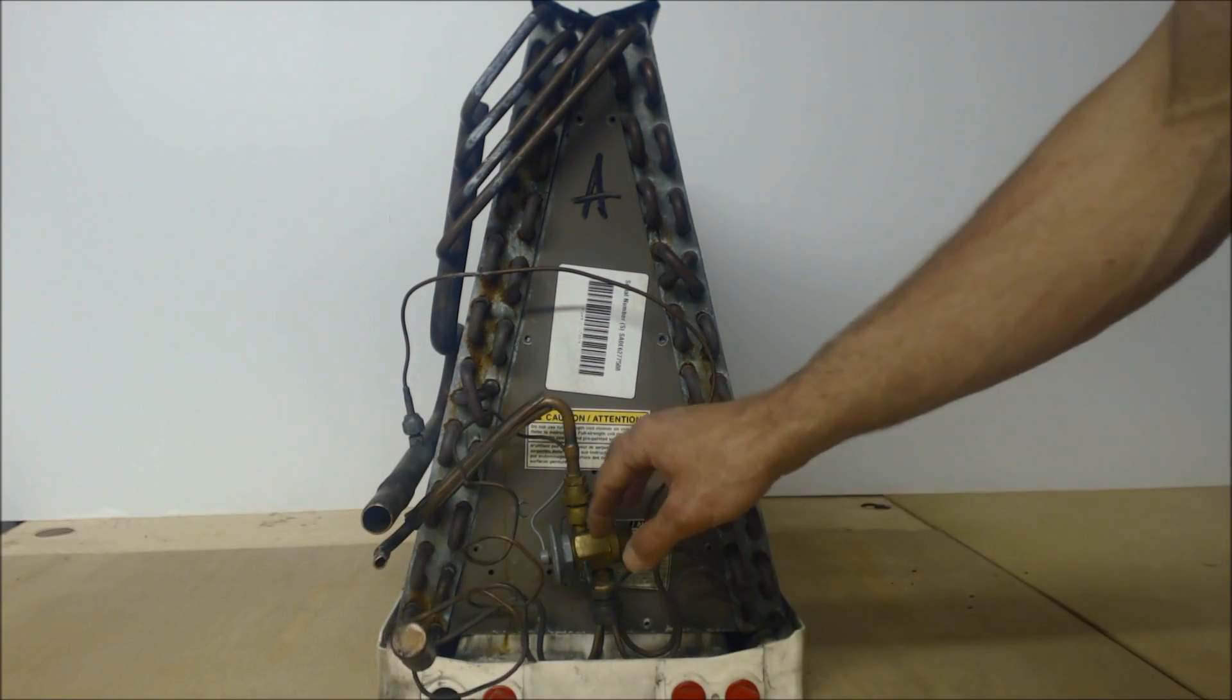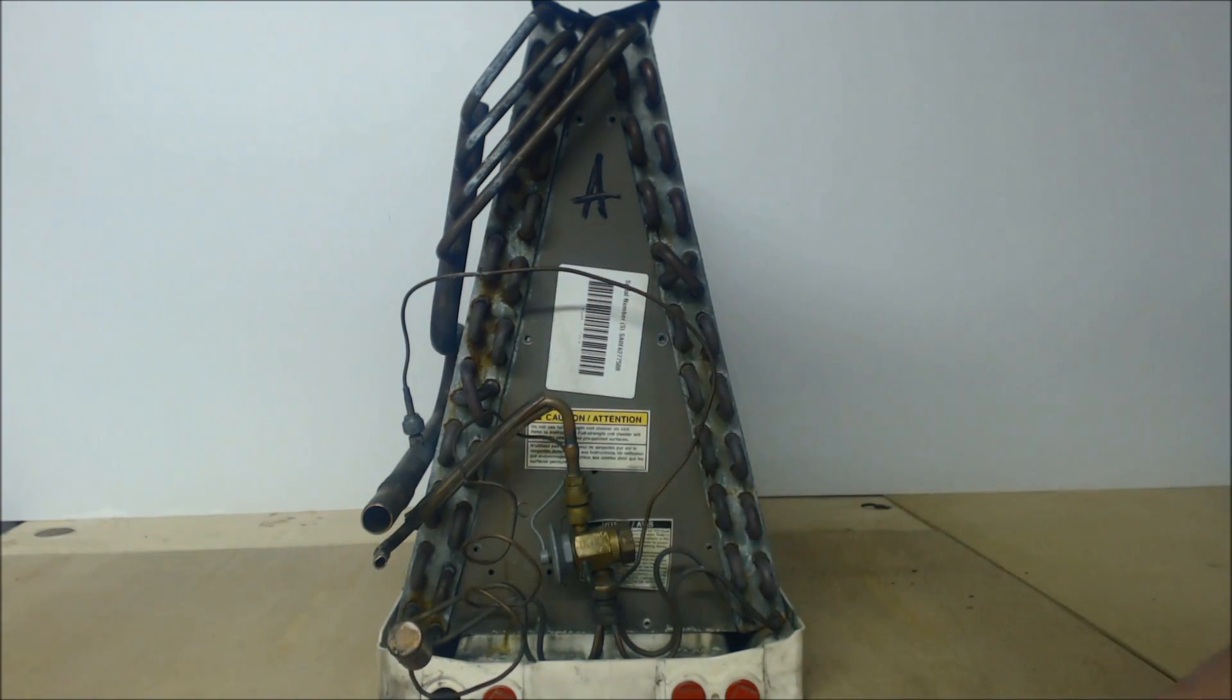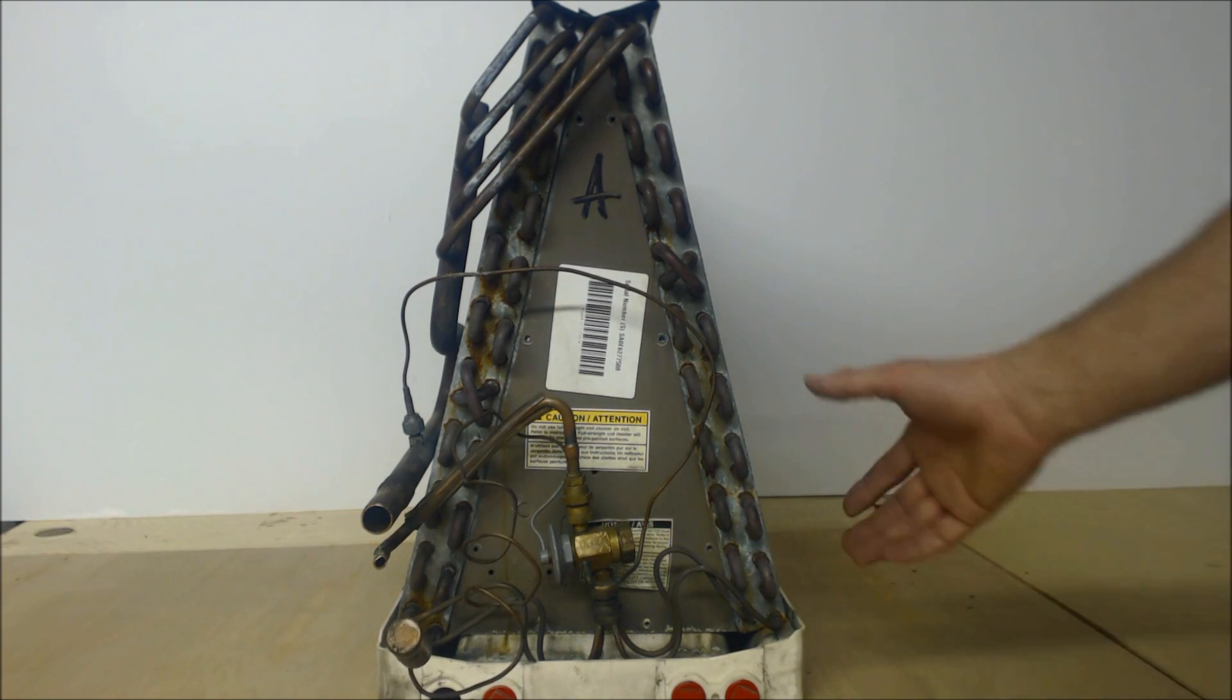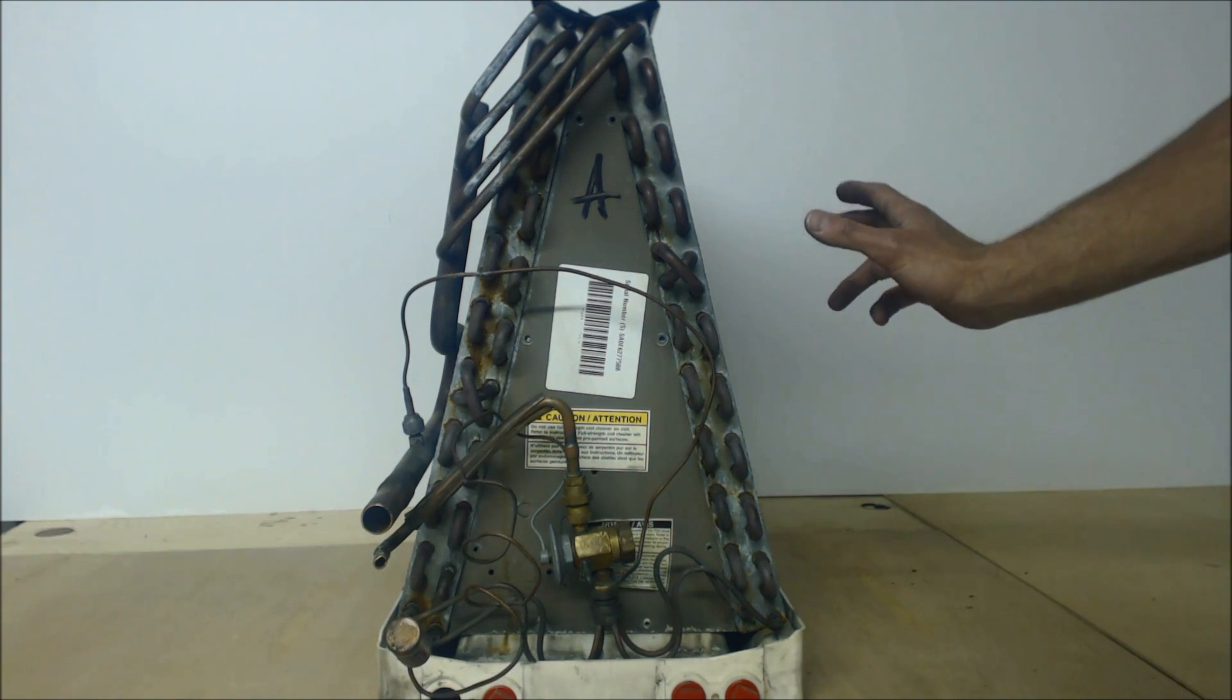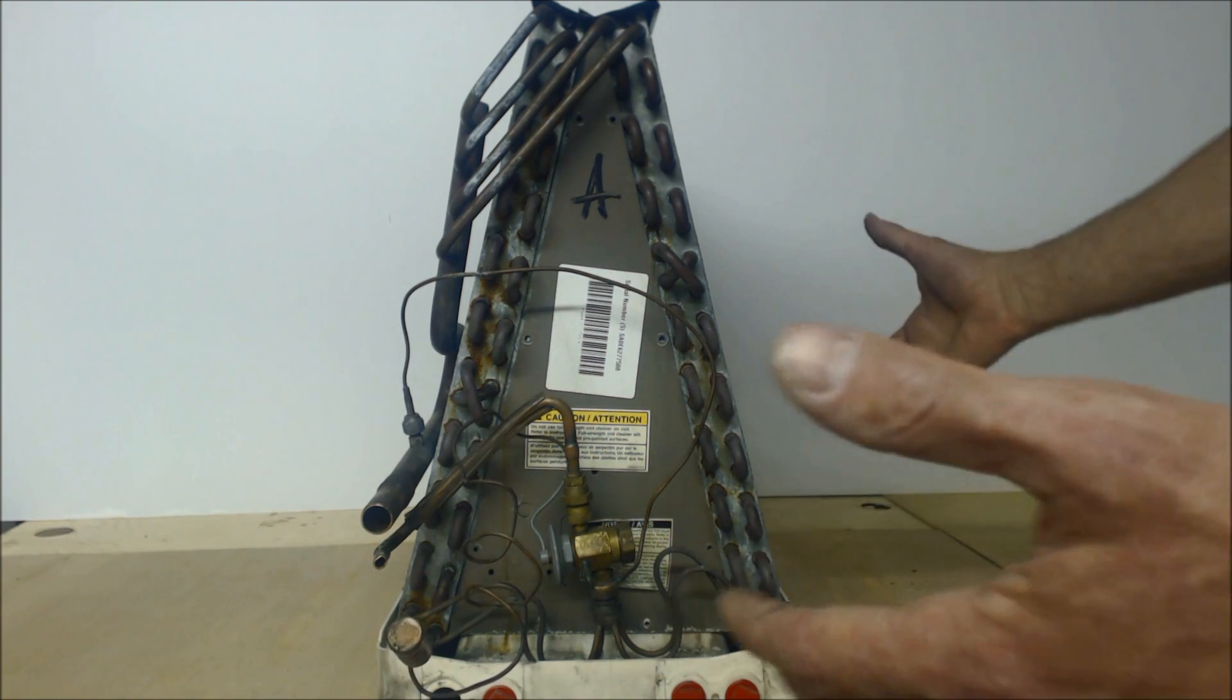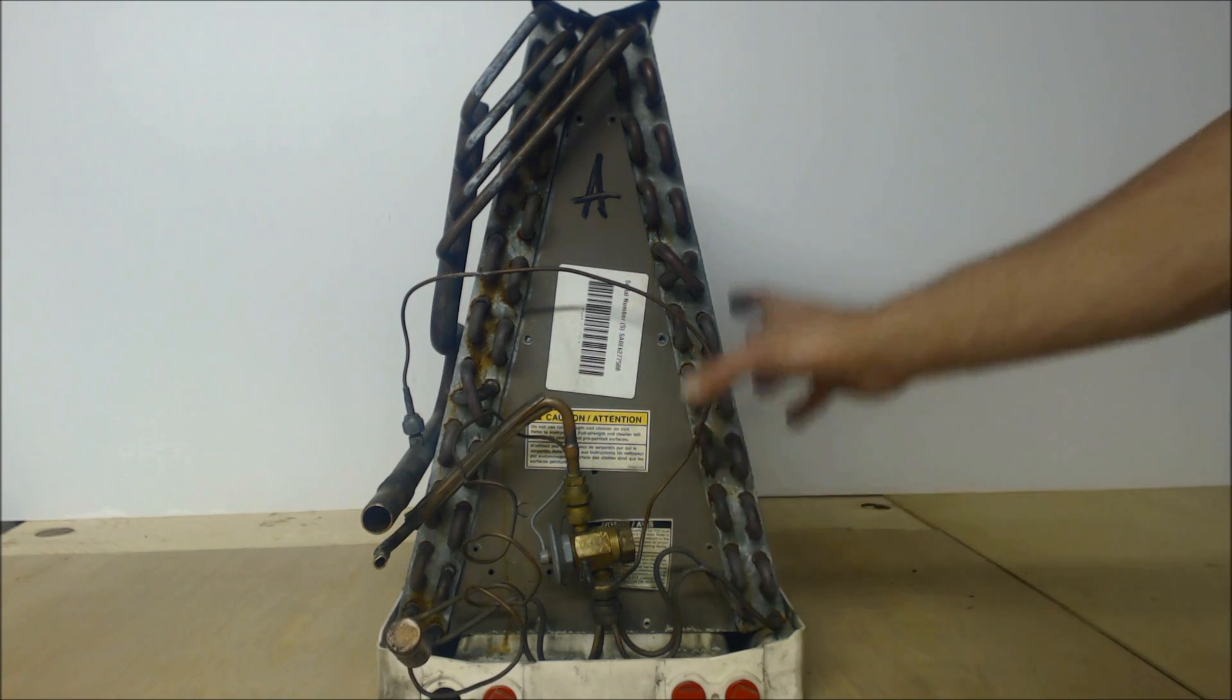If you don't have enough airflow across this coil, the coil is going to start to freeze. It's not going to be able to absorb as much heat, so the temperature will continue to get lower and lower until the thing turns into an ice cube.